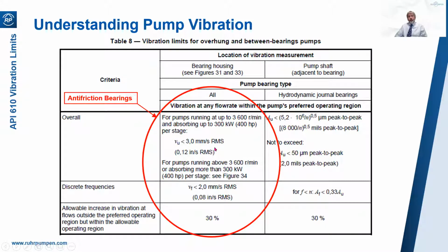Outside of that preferred operating region, so fundamentally from minimum continuous flow to 70% of BEP flow, you can have a 30% uplift on that. So 3.9 millimeters per second instead of 3, or 0.16 inches per second.